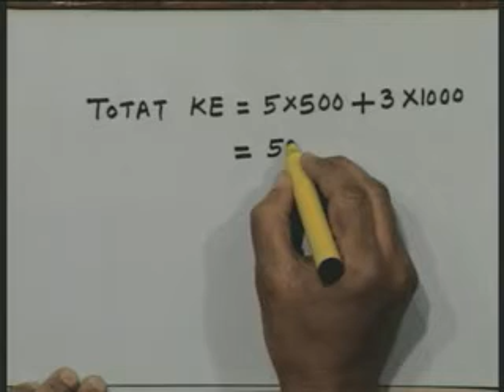Then the calculations proceed in a straightforward manner. First we find out the total kinetic energy stored in the two machines. That is, total kinetic energy will be equal to, take the basic definition, H1M1 plus H2M2. For the first machine H is 5, MVA rating is 500, plus second machine H is 3 and MVA rating is 1000. This comes out to be 5500 megajoules.